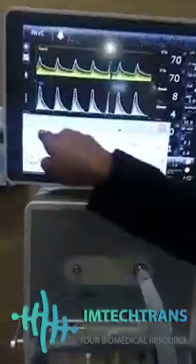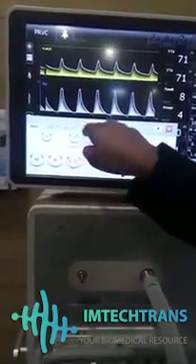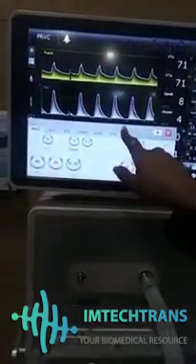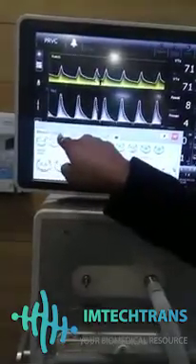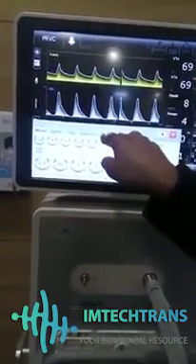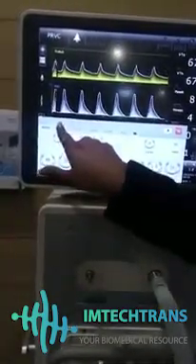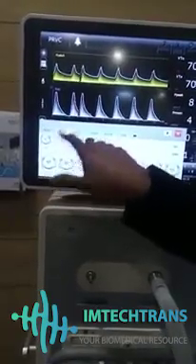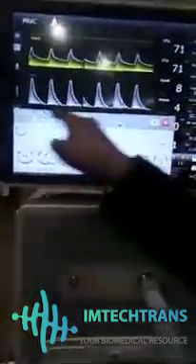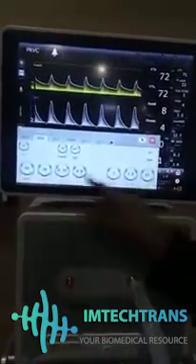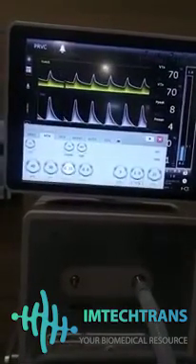So let's talk about the modes. Just press here, and you can see all the modes available in this ventilator, like PRVC, VCV, PCV, spontaneous, auto, CPR, bi-level, PRV, TCPL, O2 stream and HFV. You can choose any mode according to your patient. Like I want to select this VCV. In this VCV you can select all these parameters like tidal volume, respiratory rate, inspiration time, pause time. You can select all the parameters according to your patient from here through this knob or touch also.